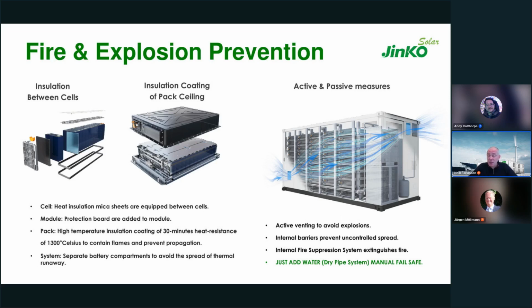So if the sprinkler fails, if the other fire suppression or aerosol fire suppression doesn't control the fire, we have the option to flood the system, to flood the battery completely. It's a well-proven, tried and tested method, and it will keep the battery safe. We don't have to do that, and other battery suppliers don't have to do that, but we choose to. We've listened to lots of people in the industry, including insurance companies and the fire and rescue service, and simply by doing that, we can control the probability of a fire or explosion event being present outside of your container, which is where you want to be.